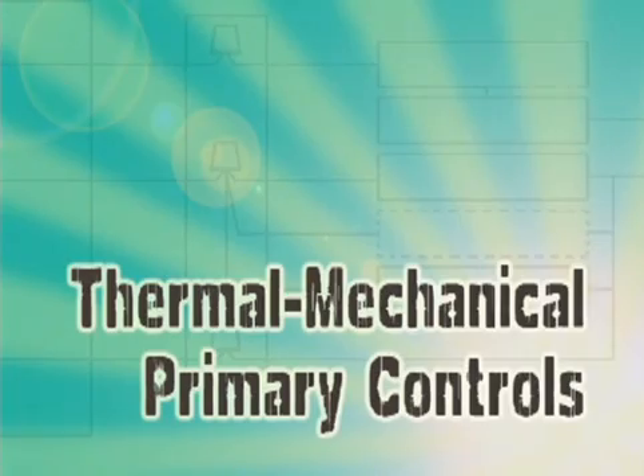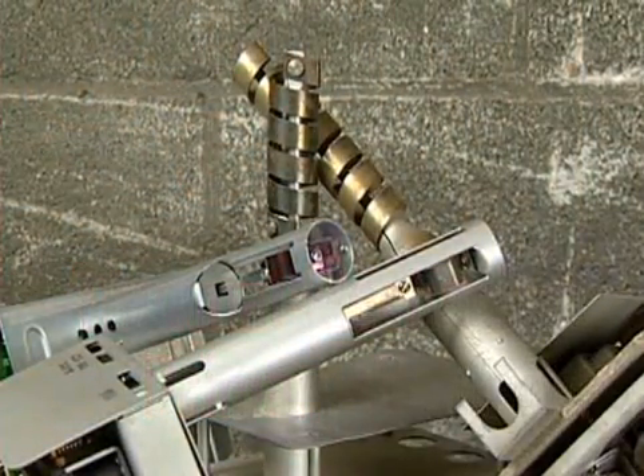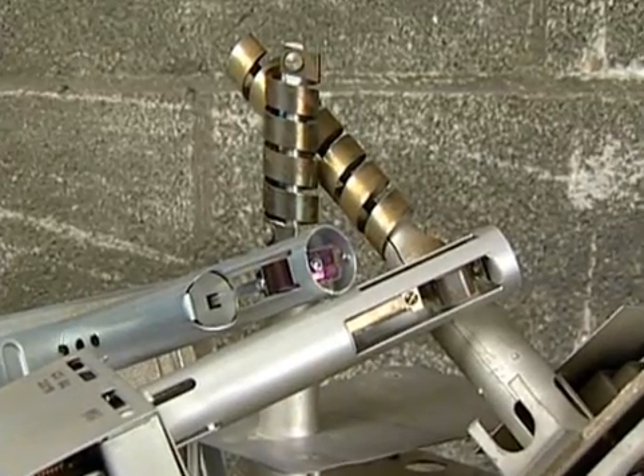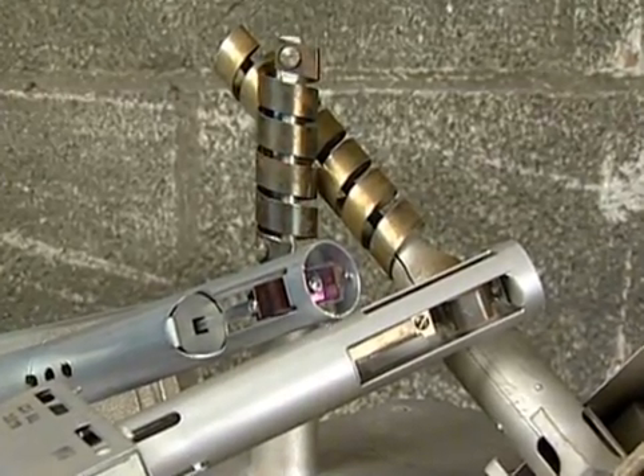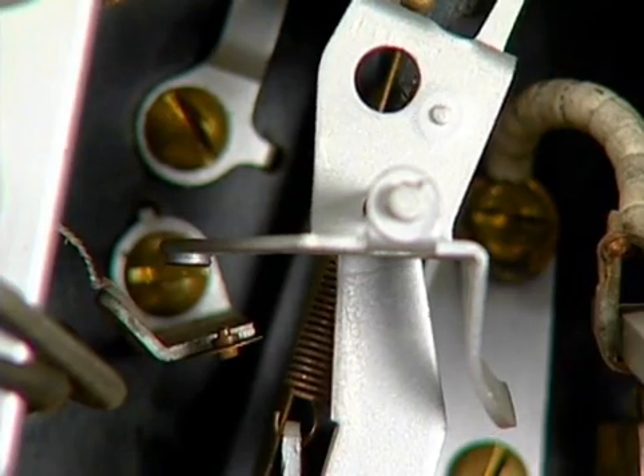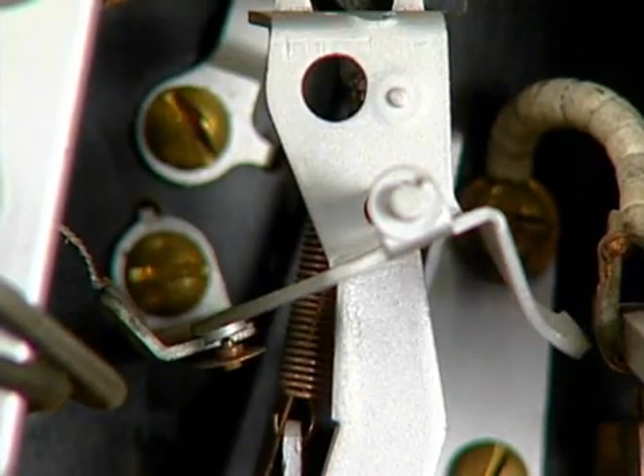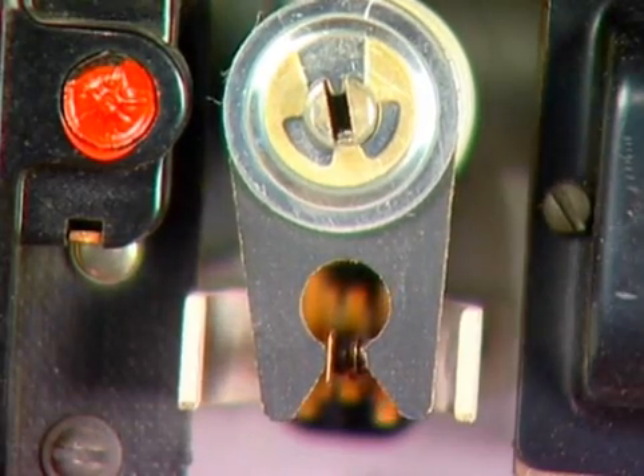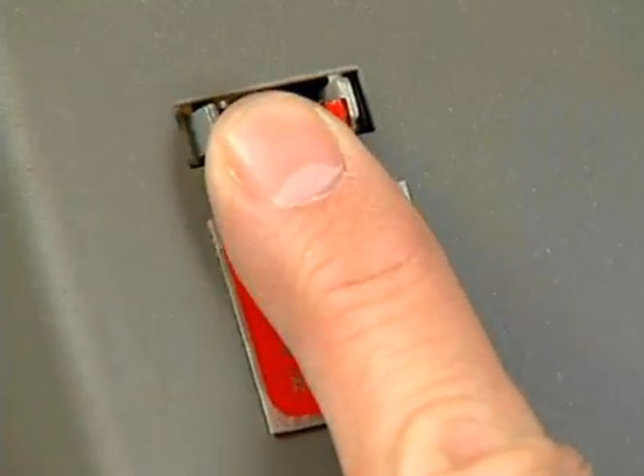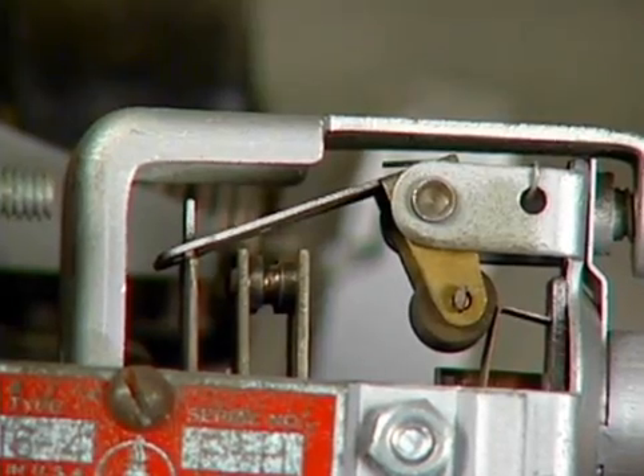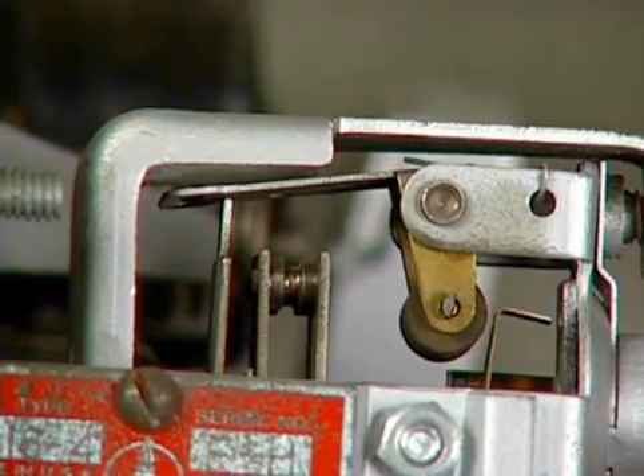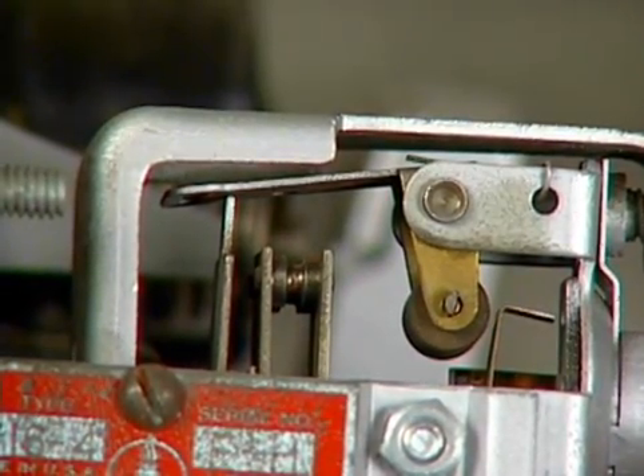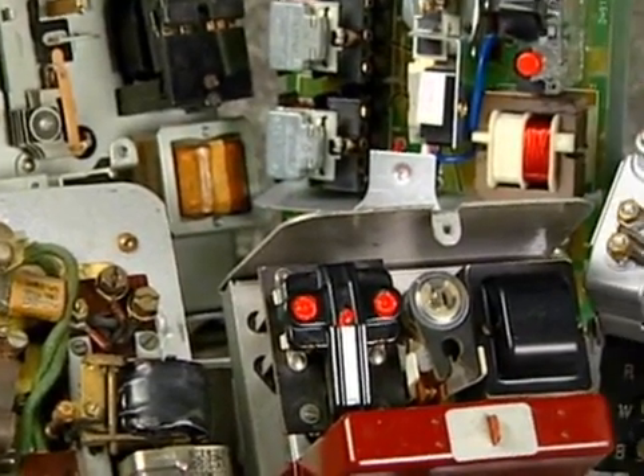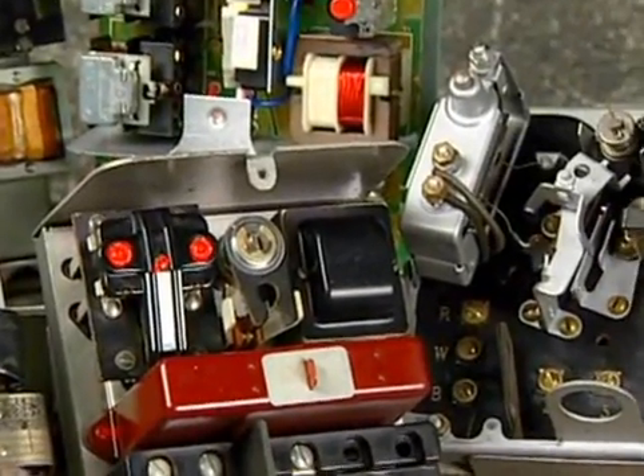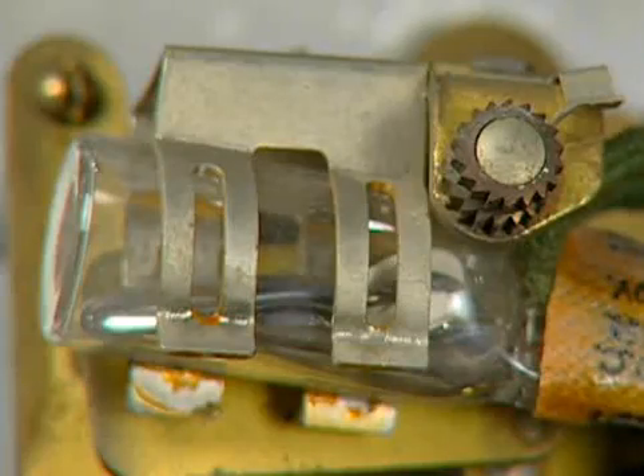Thermomechanical primary controls. Thermomechanical controls, commonly called stack switches or stack relays, utilize bimetals to detect flame and to mechanically open and close electrical contacts to provide burner control. They have spring-loaded reset buttons and a thermal safety switch that must cool before allowing the control to be removed from lockout. Through the 1960s, such stack switches were the industry's standard primary control.